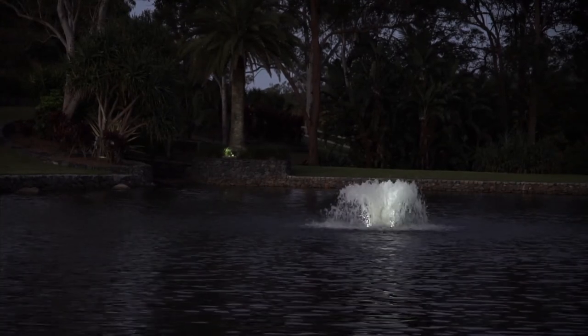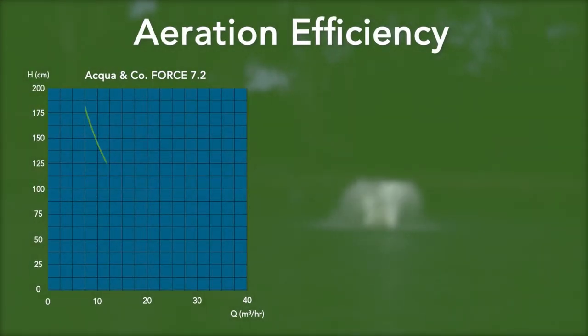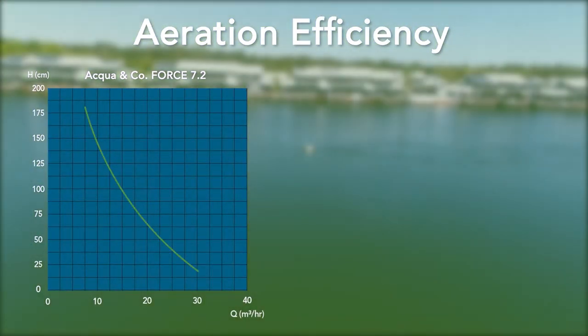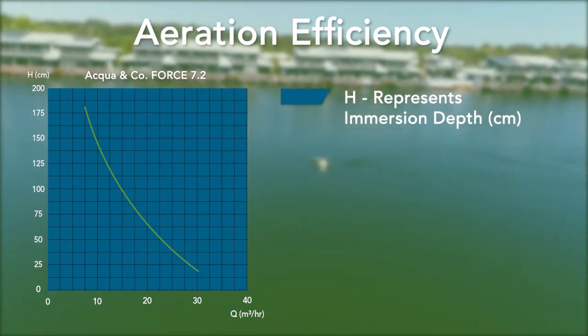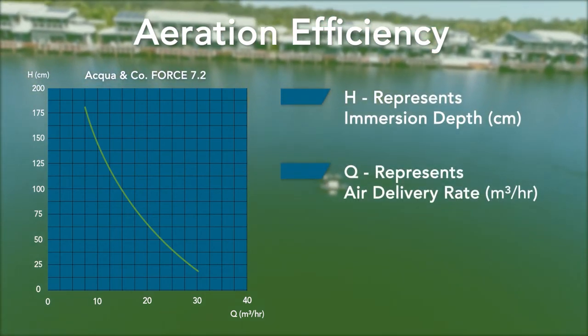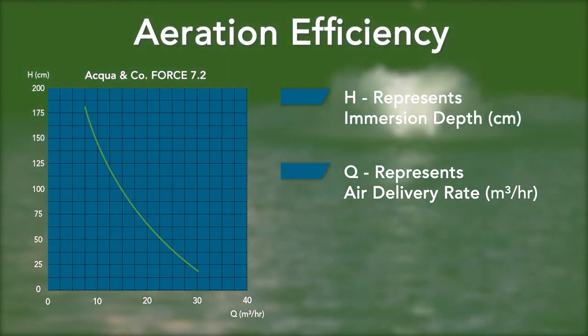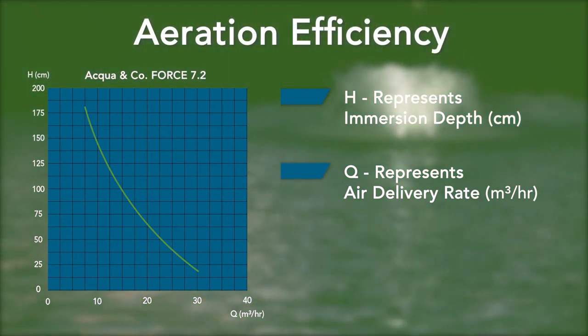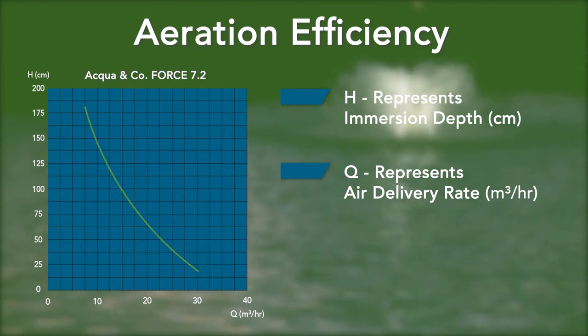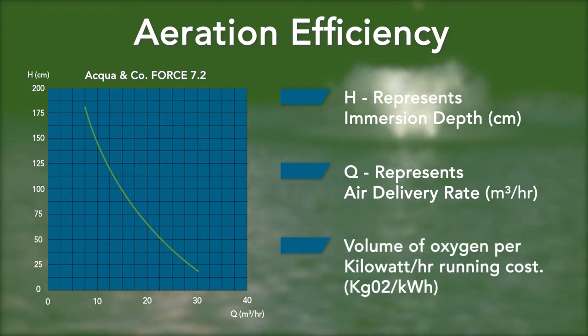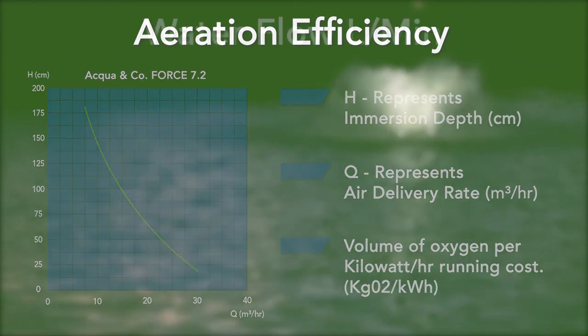So how do you choose your aeration device? There are a few things you should consider. First, aeration efficiency is an important consideration when selecting an aerator. Efficiency can be calculated by measuring the amount of oxygen transferred in relation to the energy used per nominal horsepower. Energy costs are very important and must be evaluated in practical conditions. Aerators of all kinds have different oxygen transfer rates and standard aeration efficiencies, often measured by their ability to introduce a set volume of oxygen per kilowatt-hour running cost.